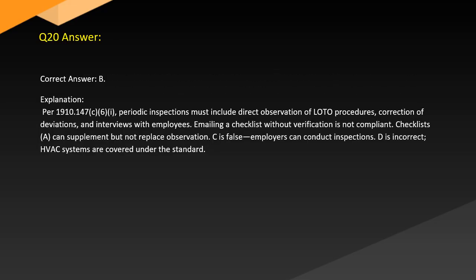Answer. Correct answer: B. Explanation. Per 1910.147 C6 I. Periodic inspections must include direct observation of LOTO procedures, correction of deviations, and interviews with employees. Emailing a checklist without verification is not compliant. Checklists can supplement but not replace observation. C is false. Employers can conduct inspections. D is incorrect. HVAC systems are covered under the standard.